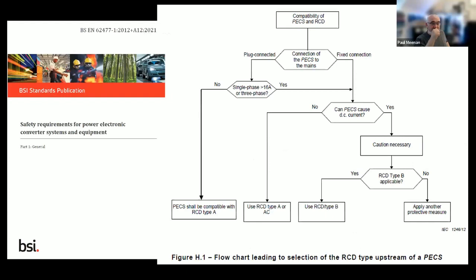If we fast forward to 2021, it's actually 2022 that came out, and it's mainly a product standard. Electricians generally don't know about it, but I find this chart quite fascinating. BS EN 62477 part 1 talks about power electronic conversion systems and compatibility with the RCD. So it's plug connected and it's greater than 16 amp or 3-phase. Then we ask, does it cause a DC current? And if it does, we take cautions, and then potentially we apply a type B RCD. And if that won't work, we then apply another protective measure. But if we have plug connected and it's less than 16 amp, then we're recommending type A compatibility.